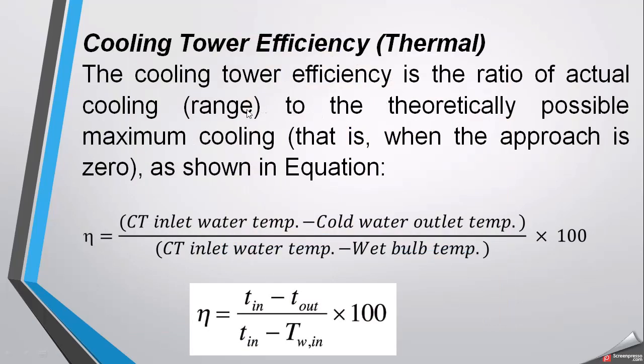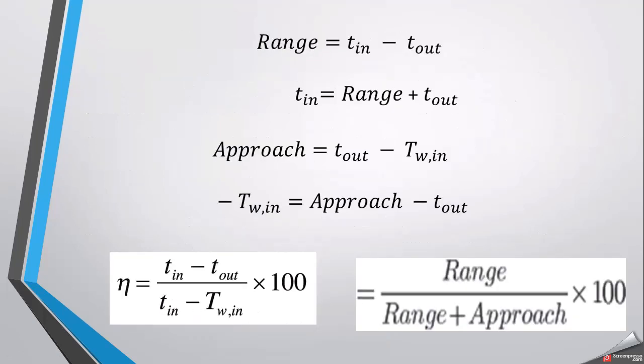Cooling tower efficiency is the ratio of actual cooling (range) to the theoretically possible maximum cooling, which occurs when approach equals zero — meaning no difference between cold water and ambient wet bulb temperature. The formula is: η = (T_in − T_out) / (T_in − T_wetbulb) × 100. Since range = T_in − T_out and approach = T_out − T_wetbulb, this simplifies to: η = range / (range + approach) × 100.